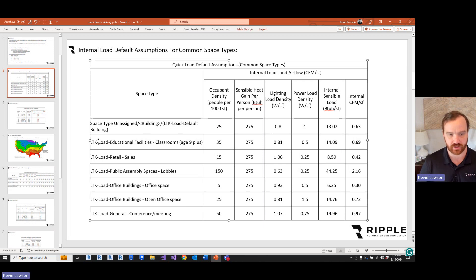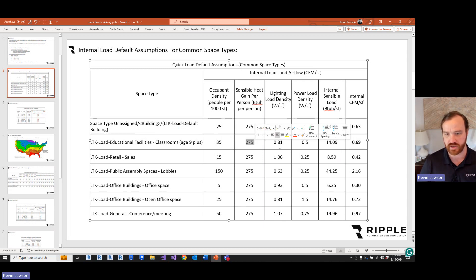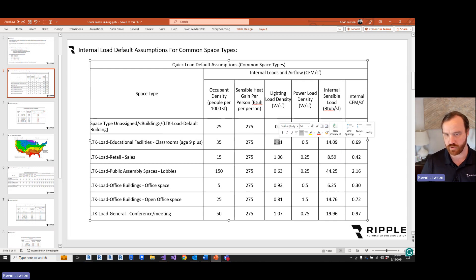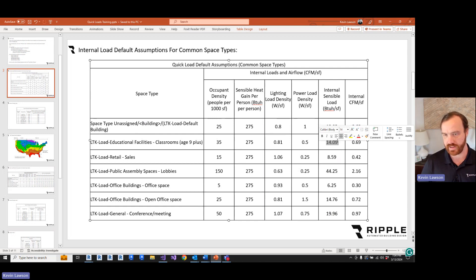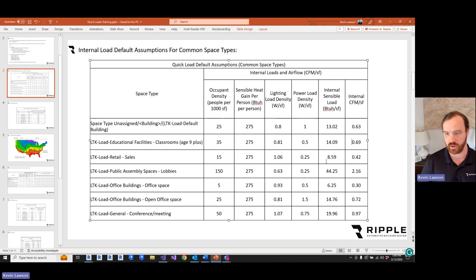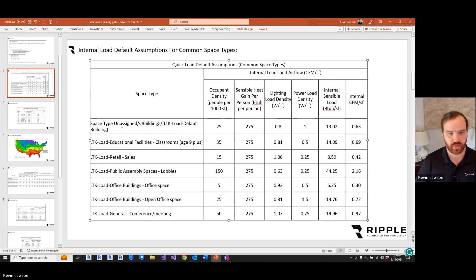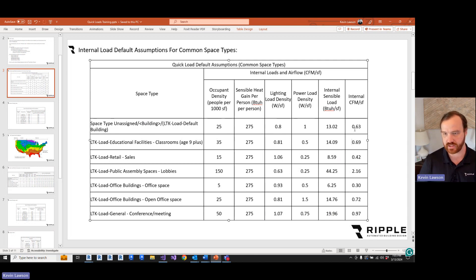For instance, a classroom is going to take the occupancy density from 62.1, assume 275 BTU per person, 0.81 watts per square foot lighting load, 0.5 watts per square foot power load. That total internal load is going to come out to 14.09 BTU hours per square foot. So to cover that, it's going to need 0.69 CFM per square foot. Now, if the occupancy tool can't decide what the space type is, it's going to leave it unassigned or building, and in that case these assumptions will be made, coming out to 0.63 CFM per square foot.